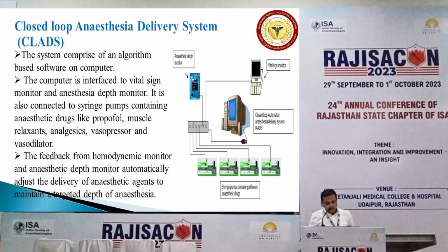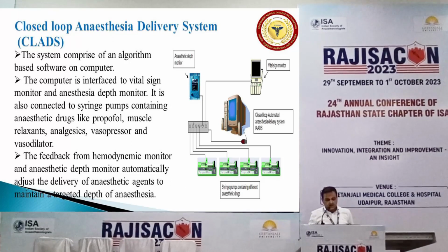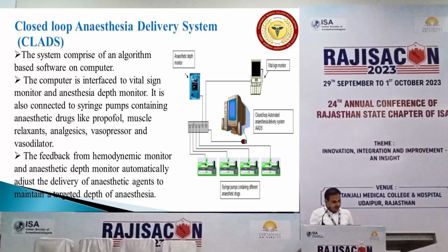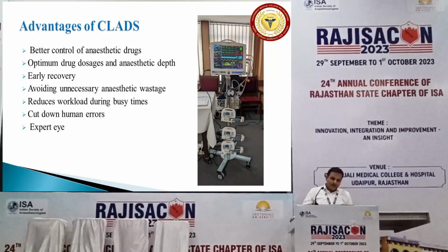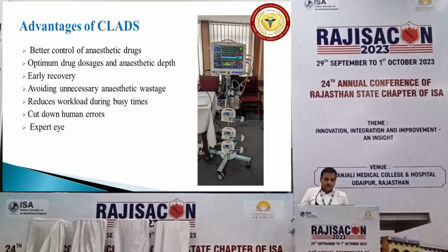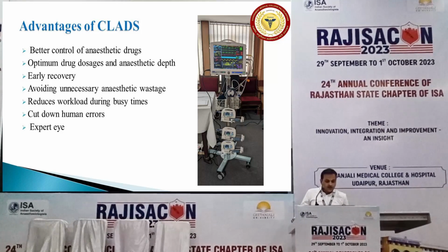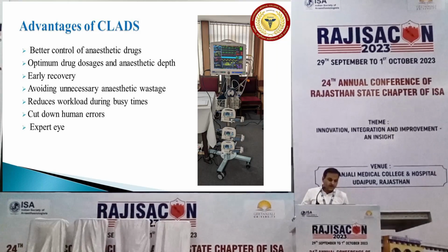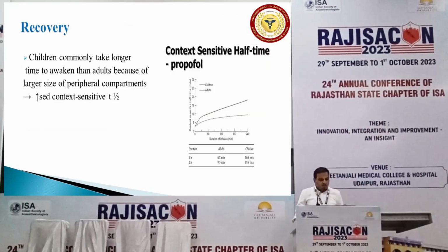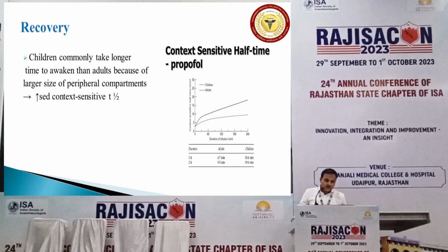The feedback from the hemodynamic monitor and anesthesia depth monitor automatically adjusts the delivery of the anesthetic agents to maintain the target depth of anesthesia. Advantages of the CLAD: better control of the anesthetic drug, optimum drug dosage and anesthetic depth, early recovery, avoiding unnecessary anesthetic wastage, reduced workload during busy hours, cutting down human errors, and it is an expert eye.